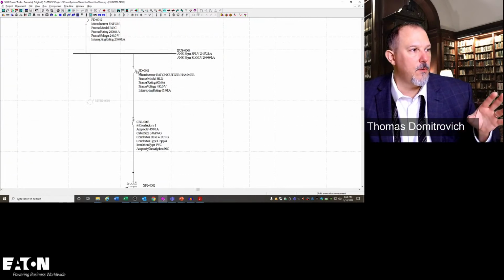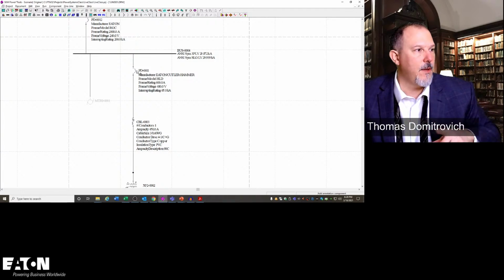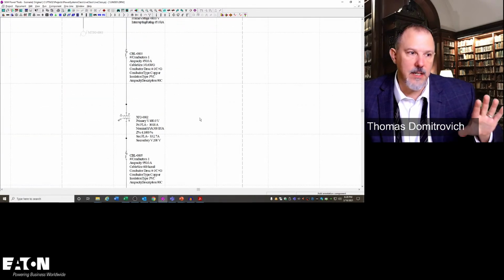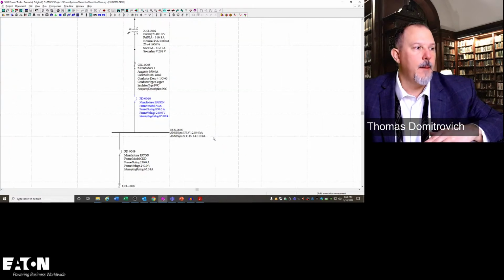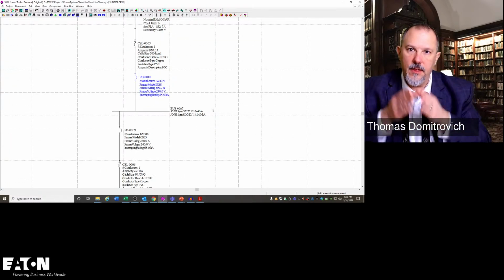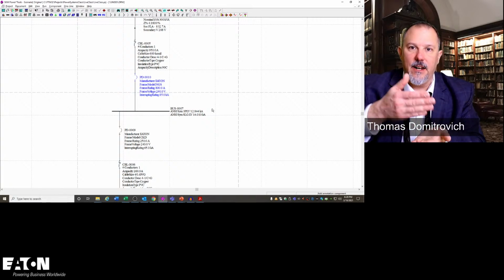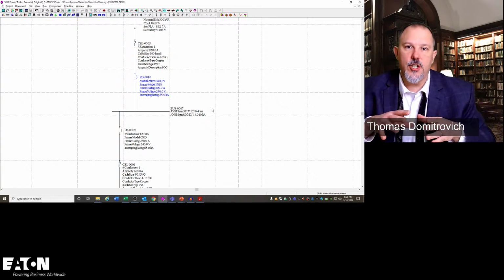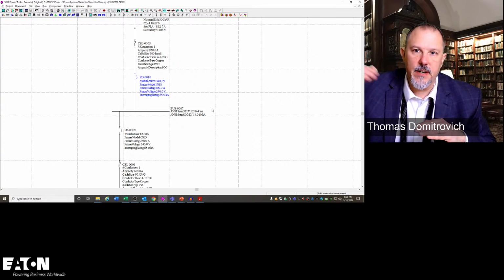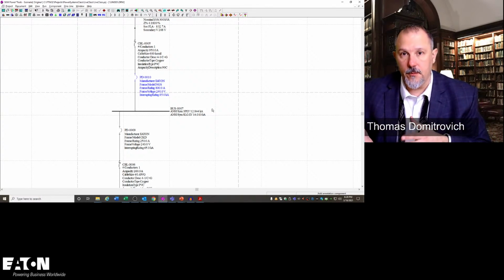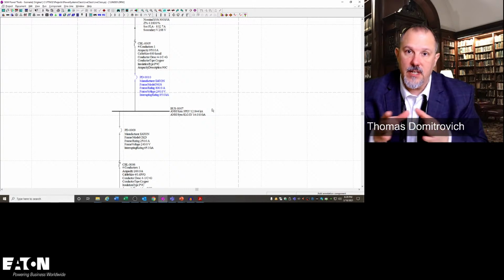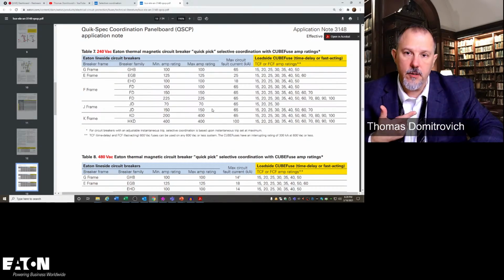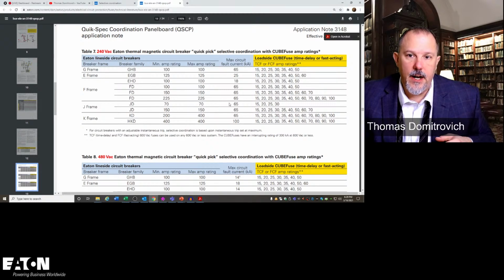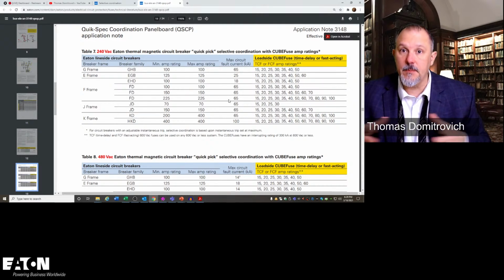And then I could go up to, and we'll talk about going around a transformer here in a second. But what I'm doing is starting from the furthest part, picking my overcurrent devices. If I'm using circuit breakers, they are current sensitive. I need to evaluate at an available fault current. If I want to make my upstream overcurrent device smaller and not an electronic trip unit, I can put a fuse downstream and use the tested pairs from our literature that show I can put a 100 amp fuse downstream of an FD 225 and selectively coordinate up to 65,000 amps. That gives me a lot of breathing room.